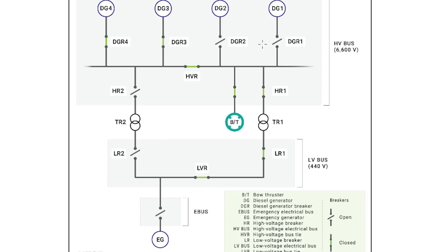The line marked HVR shows all generators connected to this high voltage bus. Normally in operation, you'd have two generators on like this and two of them off, switched off. You can tell these are in the open circuit configuration. When the ship is running, two of the diesel generators are operating.